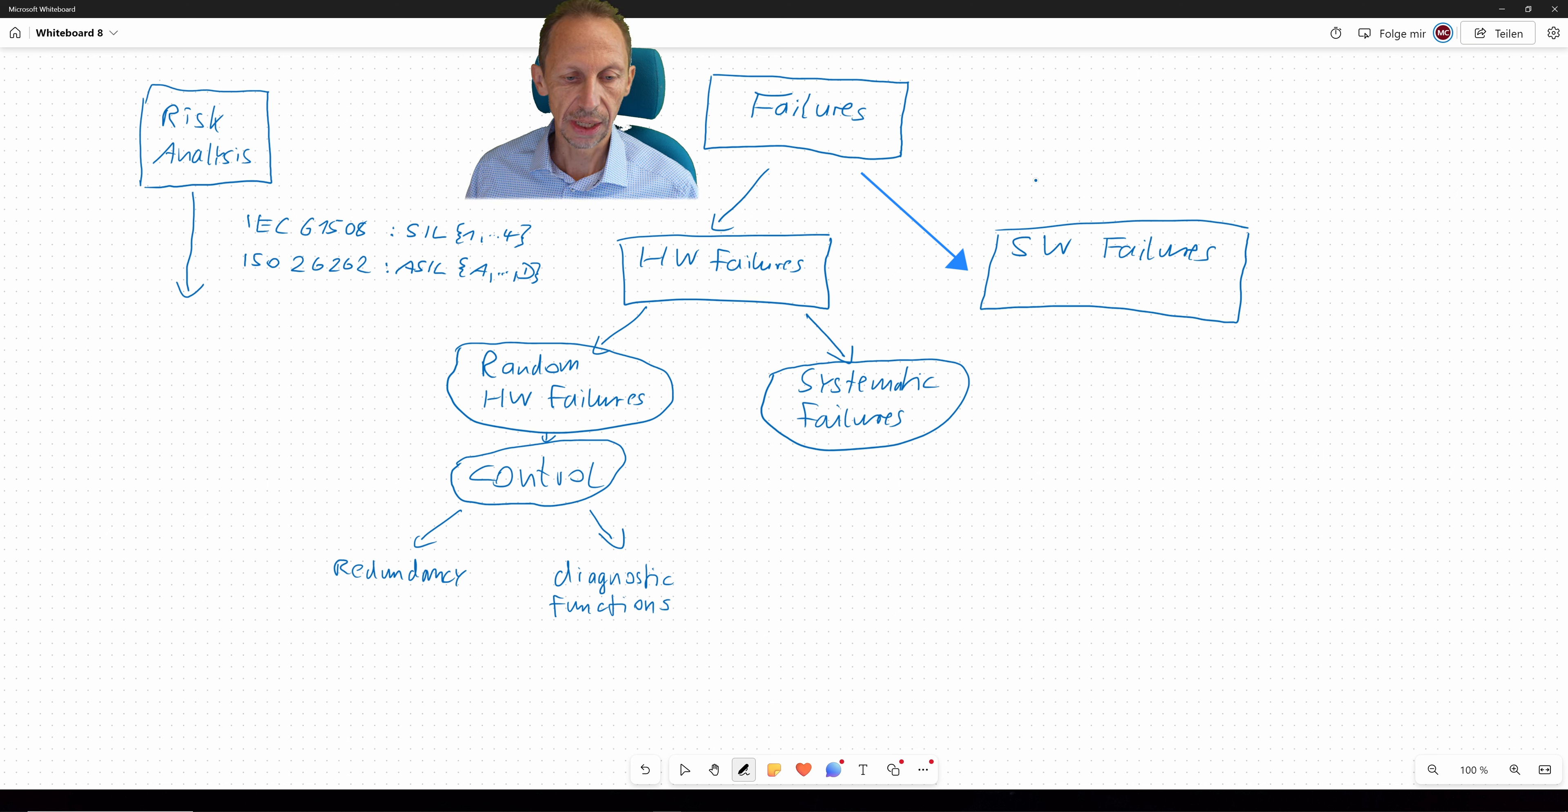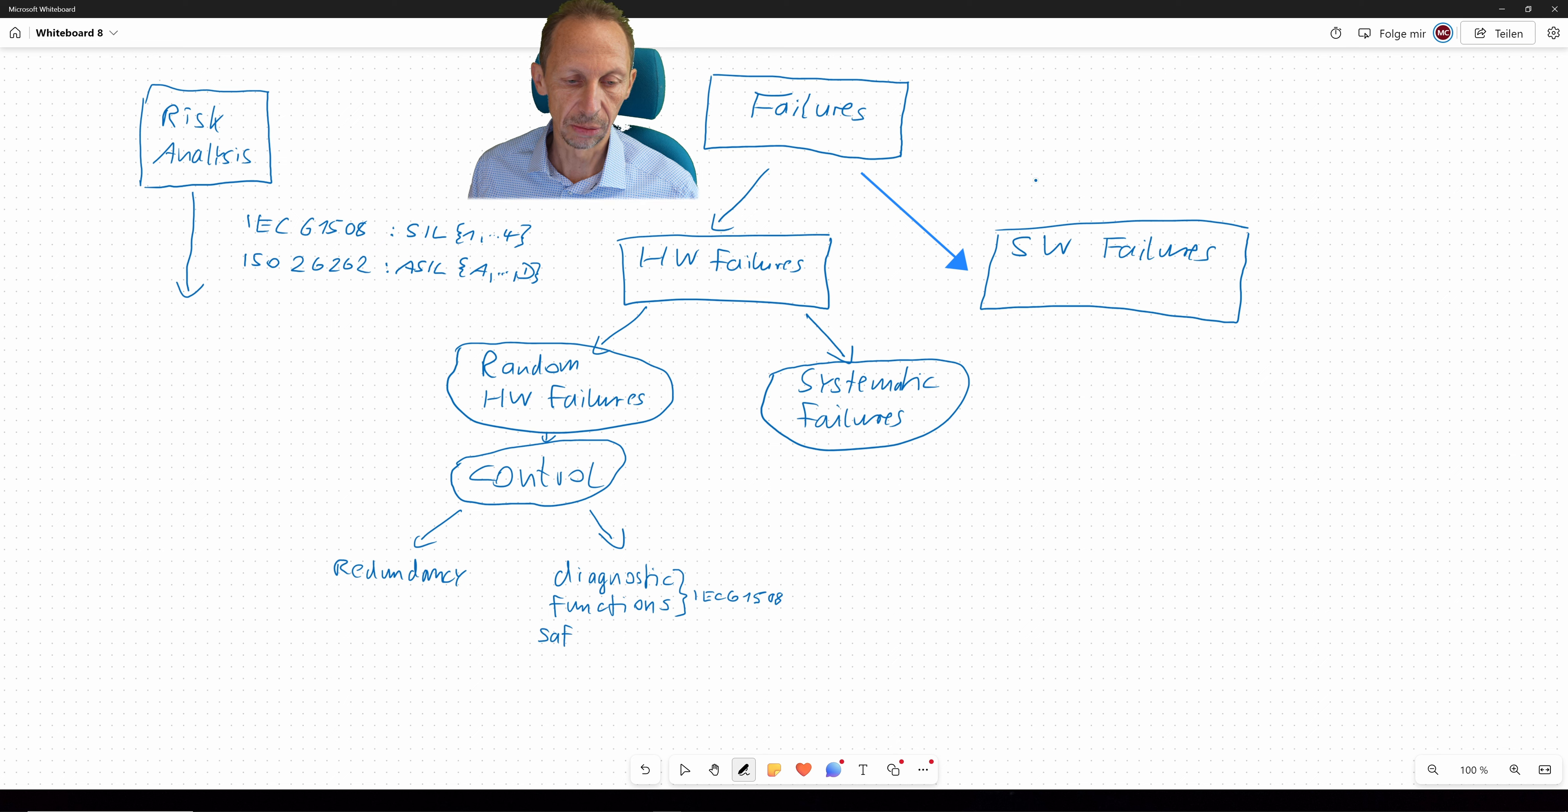A diagnostic function, for example, regarding a power supply, let's have a power supply where we have a voltage regulator. And in that case, we have this voltage regulator called a so-called intended function. So this is the function I'm intending to do, regulating the voltage. And on this voltage regulator I have a diagnostic function that is capable to detect over voltage or under voltage, for example. And this is called diagnostic function in the IEC 61508. And it's called safety mechanism in the automotive relevant standard.